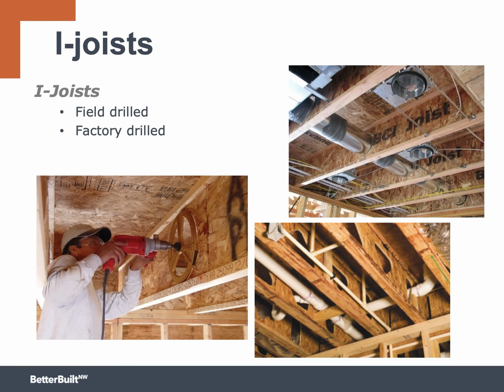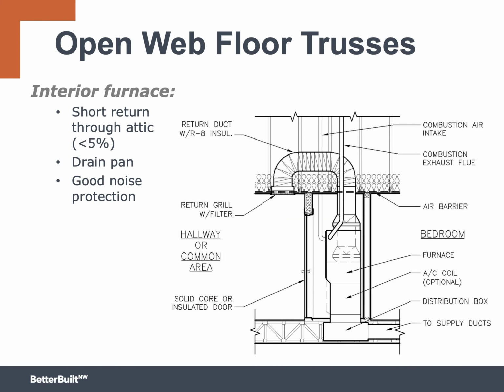You can also use I-joists in a similar way to the open web floor trusses. They can be ordered from the factory with holes already in the appropriate locations, or they can be drilled in the field as long as you have the proper hole size according to code. Here's a configuration that many builders are using. It's a downflow furnace on the second floor. The air is pushed down into a supply trunk in the floor cavity, and from that supply trunk you can attach all kinds of branch ducts to all parts of the building.